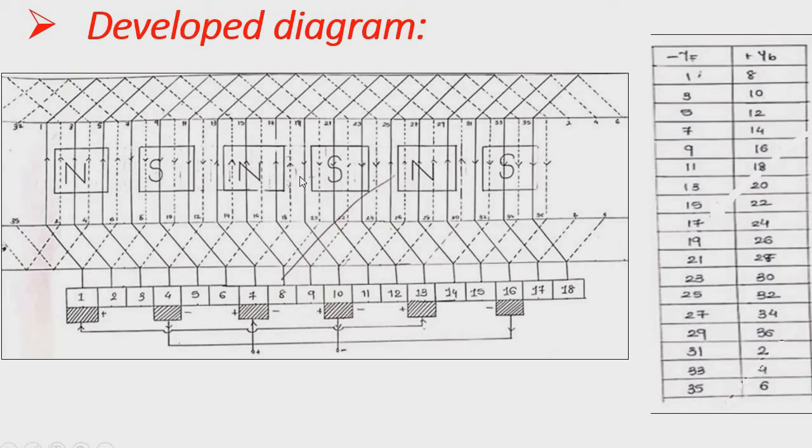So now after drawing all these conductors, we have to follow the winding table. The winding starts from conductor number 1. So 1 is connected with 8; 1 is a front conductor and this is a back conductor. So 1 is connected like this to 8, and 8 is a back conductor, that's why it is drawn in dotted form.